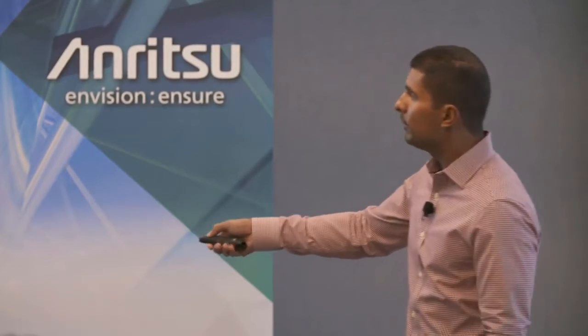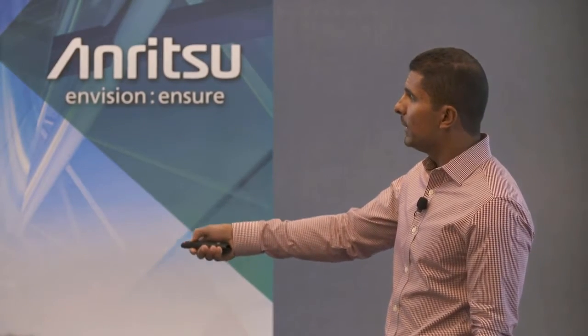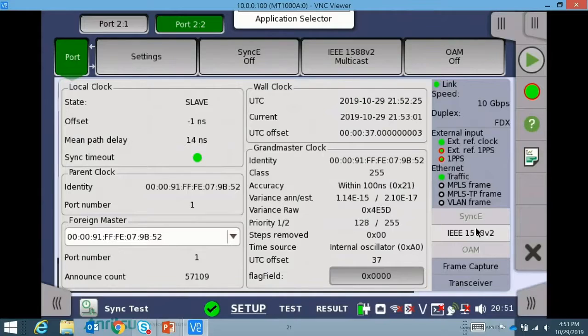From a field perspective, this would be your installation and maintenance test. This would be your ops test. This is your go, no-go, pass, fail. Is it working or is it not working? You go out in the field and you connect this, and there's a couple of things you're going to see. First, there's your grandmaster clock information. There's the identity. Here's the one you're looking for. Do they match? It tells you all of the information, the class, steps removed, the time source, everything that's being reported inside your PTP frame is being read here.